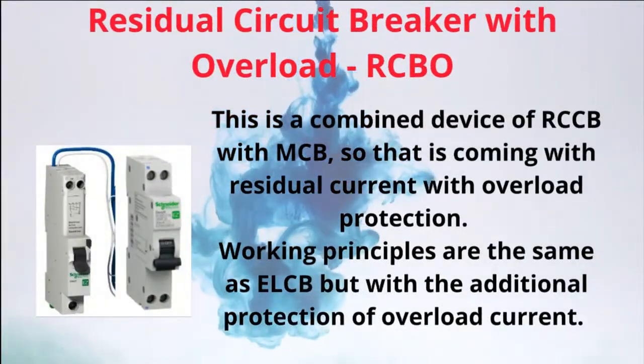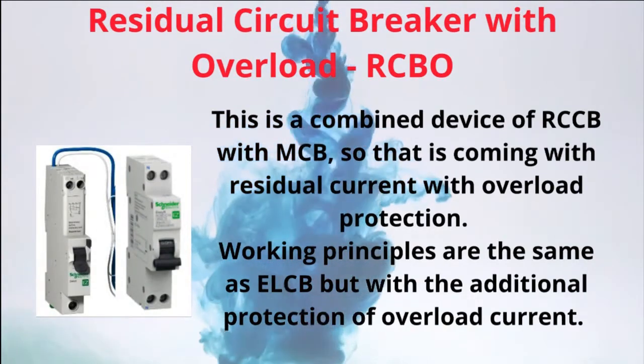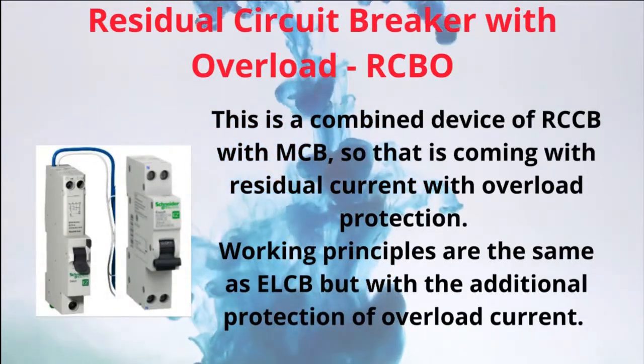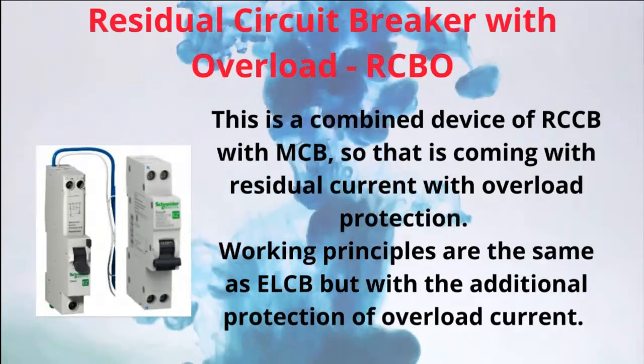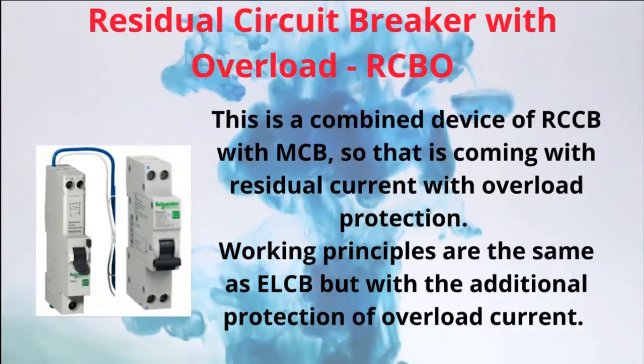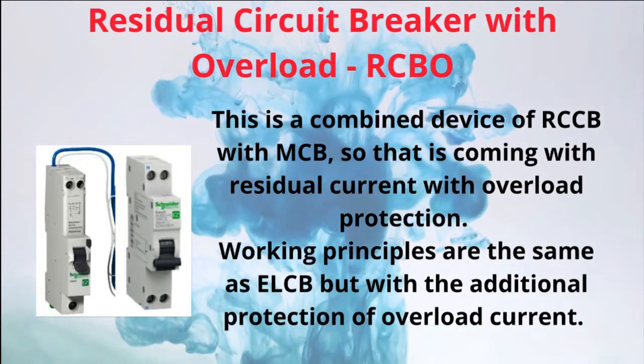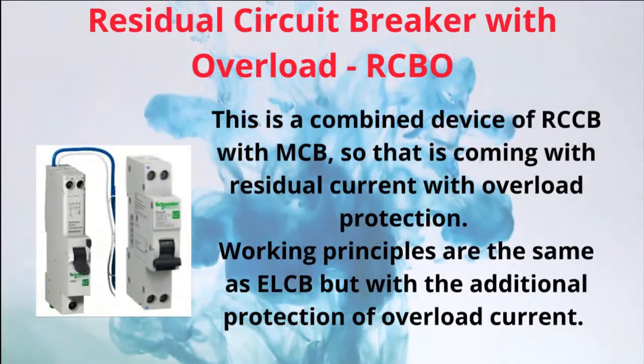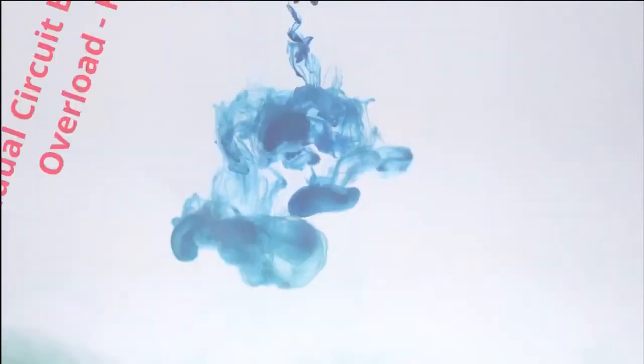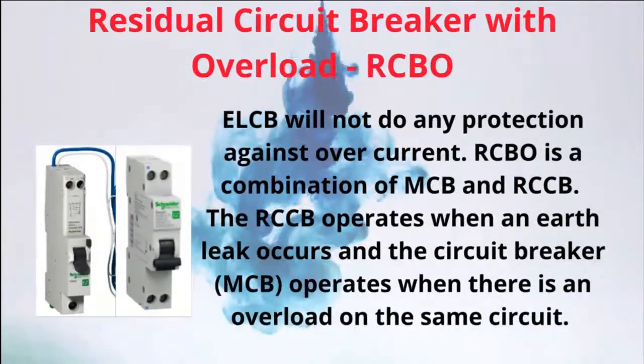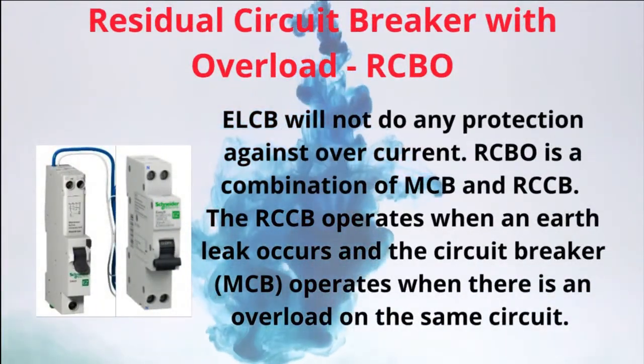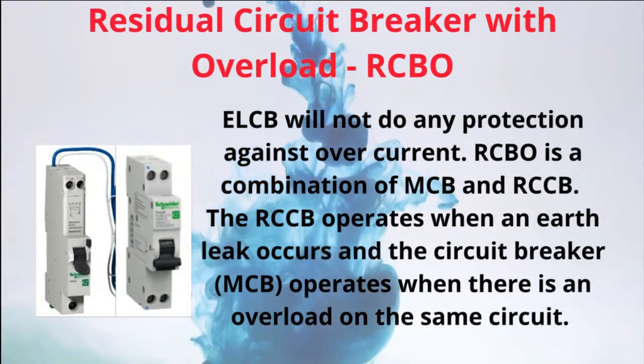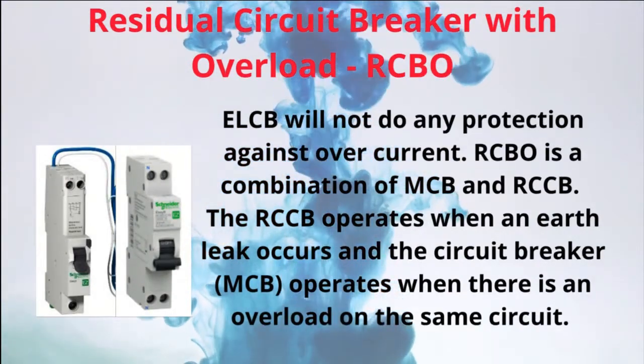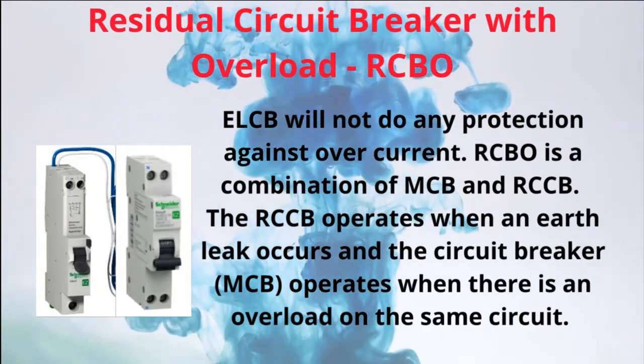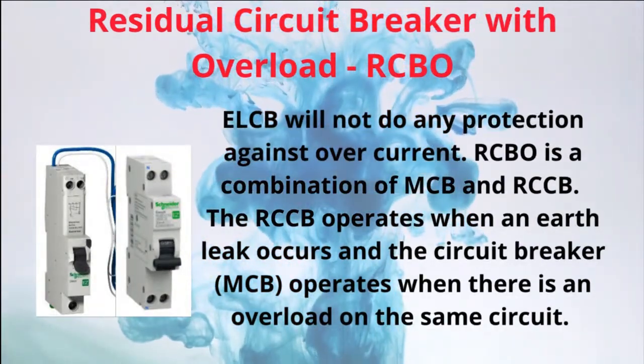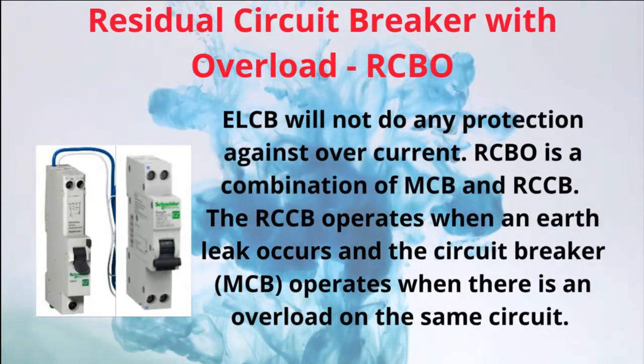RCBO, residual current breaker with overload. This is a combined device of RCCB with MCB, so it comes with residual current and overload protection. The working principle is the same as ELCB but with the additional protection of overload current. ELCB will not give any protection against overcurrent. RCBO is a combination of MCB and RCCB. The RCCB operates when an earth leak occurs and the circuit breaker operates when there is an overload on the same circuit.